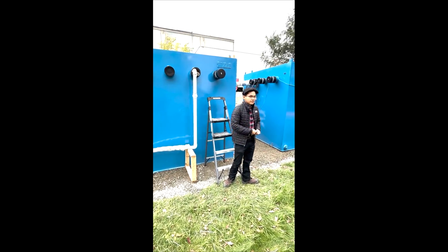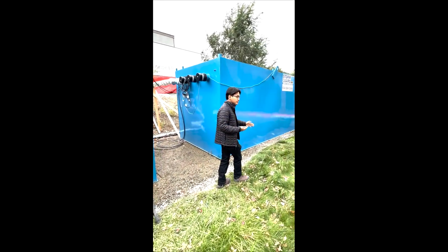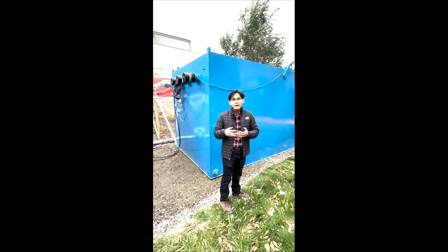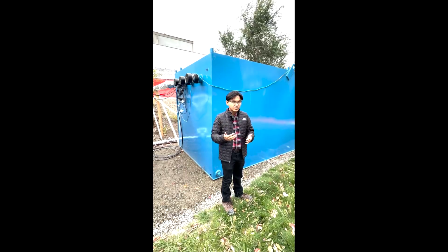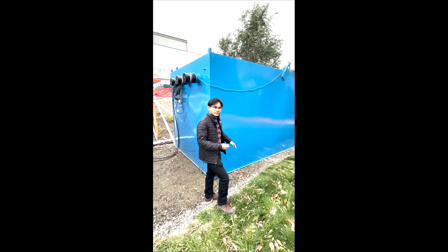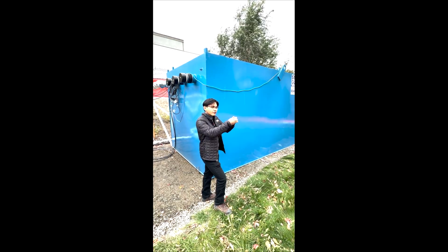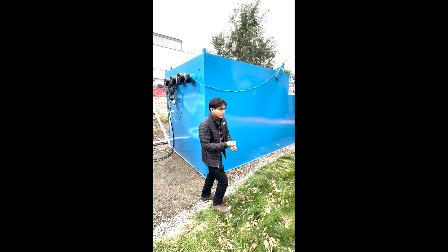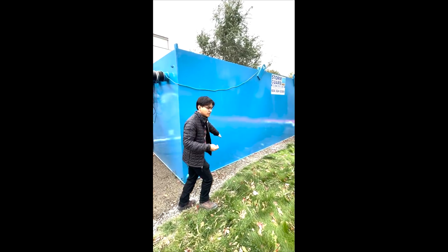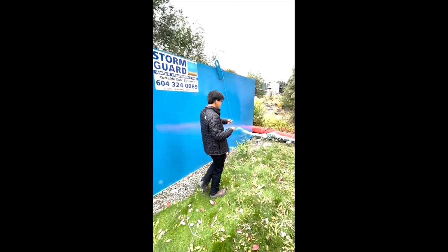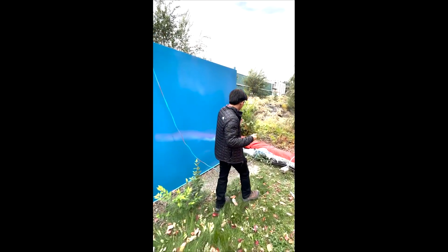And all the clean water is going to this tank, which is serving as another way to ensure that we're not adding or dumping anything to the environment, because this tank gives us some settling time. It allows the water to have time for anything to fall out, and it just settles at the bottom of this tank. And so it spends time in this tank before it gets discharged back to the lake through this outlet.